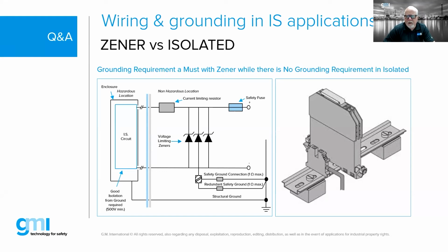So it's important to understand that if we're taking that DIN rail and mounting it inside of an enclosure, and that enclosure might be a metallic enclosure, we need to make sure that we're using isolated standoffs for that DIN rail, as opposed to just putting it on standard DIN rail where we might have clean earth or non-clean earth. So we have to be very careful with our installation of Zener barriers inside of panels.